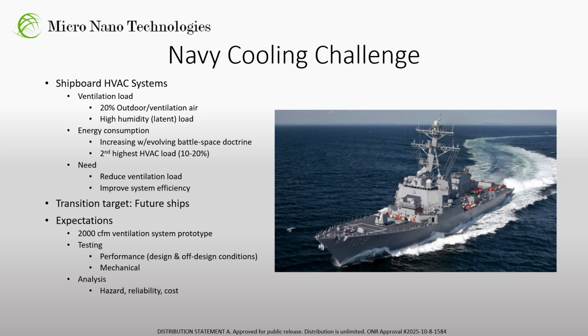In this program, a working prototype of a 2,000 cubic feet per minute ventilation system using new technology will be developed and experimentally tested to demonstrate its ability to reduce the ventilation latent load and improve shipboard HVAC system efficiency. This prototype, sized for 10 tons of cooling when exposed to summer design conditions and 30 kilowatts of heat when exposed to winter design conditions, will experimentally validate the system's performance over a variety of airflow rates and inlet conditions at design and off-design conditions. In addition to these performance tests, supporting analysis and mechanical testing will be conducted to demonstrate the viability of this technology to operate in the naval environment.